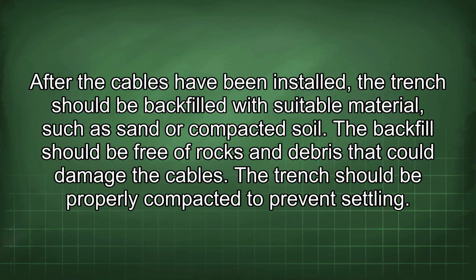After the cables have been installed, the trench should be backfilled with suitable material, such as sand or compacted soil. The backfill should be free of rocks and debris that could damage the cables. The trench should be properly compacted to prevent settling.